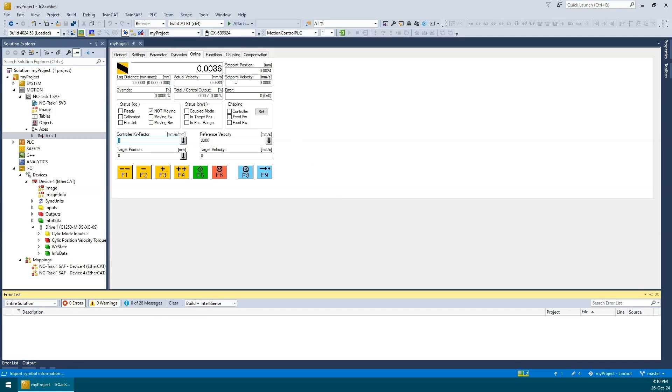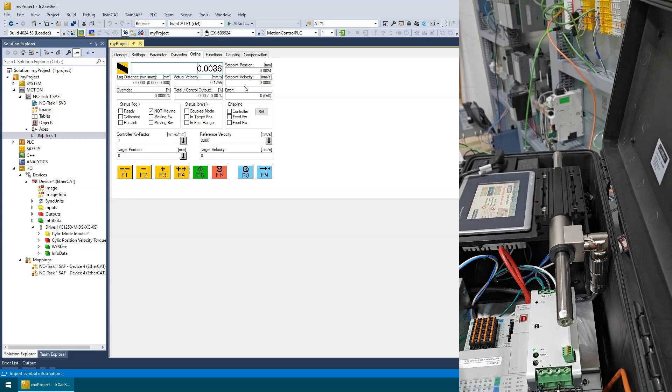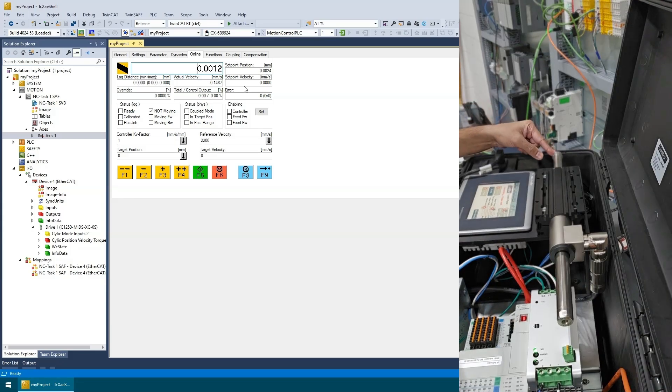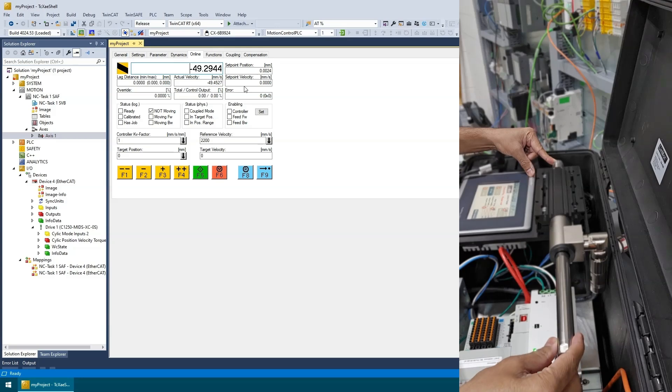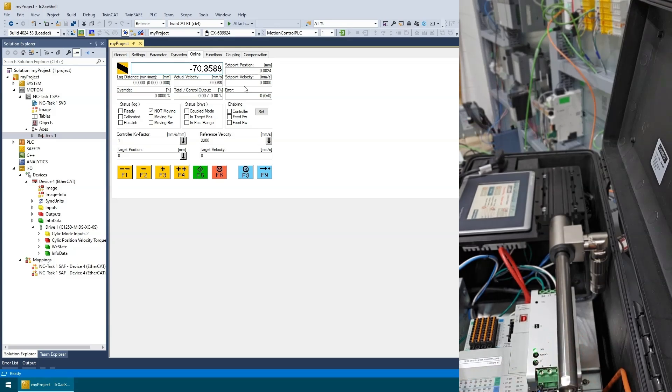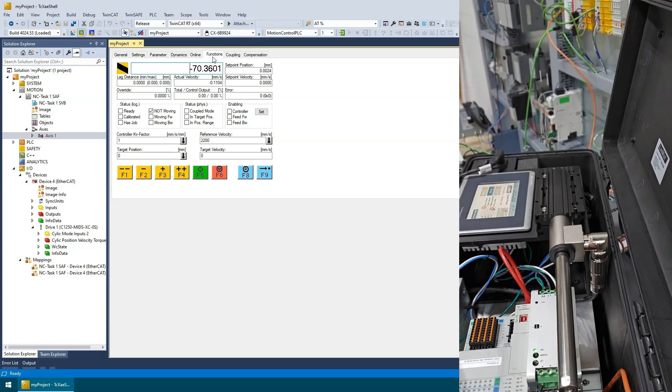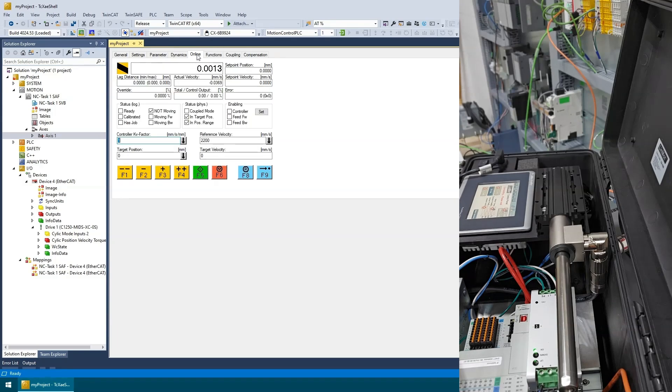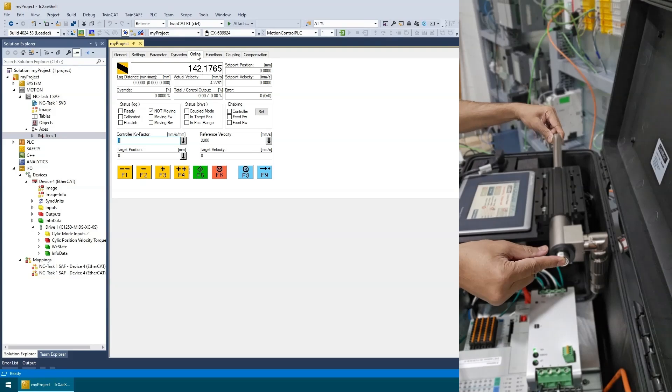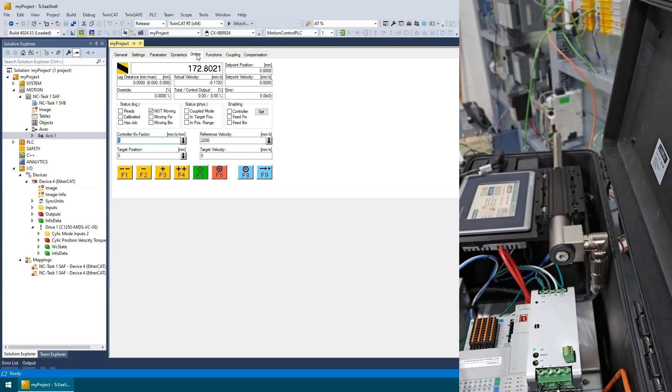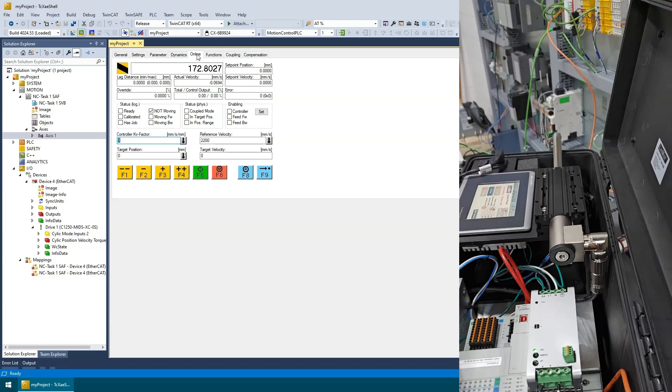Therefore, we will need to physically move the actuator position to the desired home position and then zero the position manually. This will be my home position, so I will set this position as zero. Now I will move the actuator to the other extreme end and note the feedback position. Looks like the total travel is 172.8 millimeters.